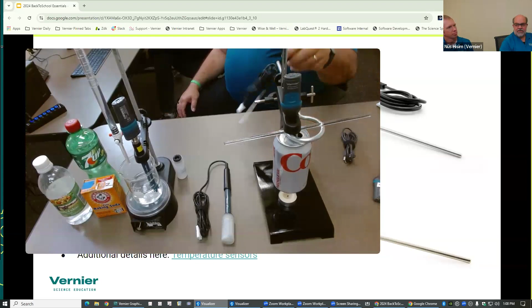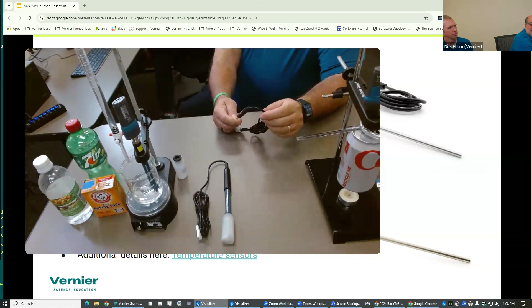A couple of things to be aware of, though, with the probes. If you have this style, let me get this experimental setup out of the way. If you have this style with the cable, please don't wrap the cable around the probe. If you do that, you put a lot of strain right here, and if the wire breaks here, we can't fix it. So when you're storing the cable, wrap it around itself, use a rubber band, or I love using these Velcro strips.